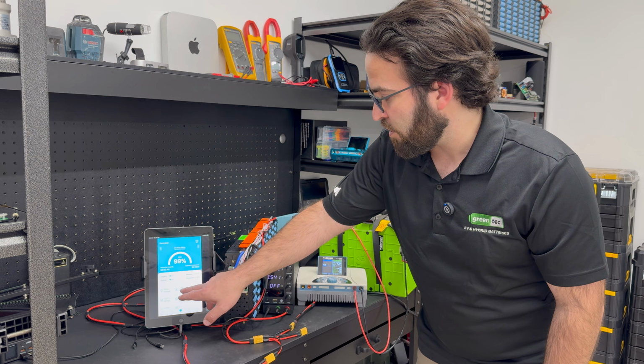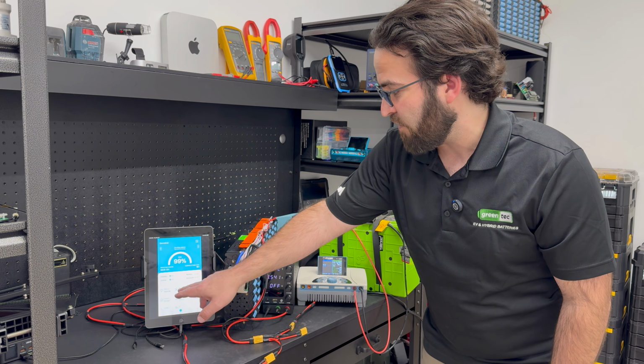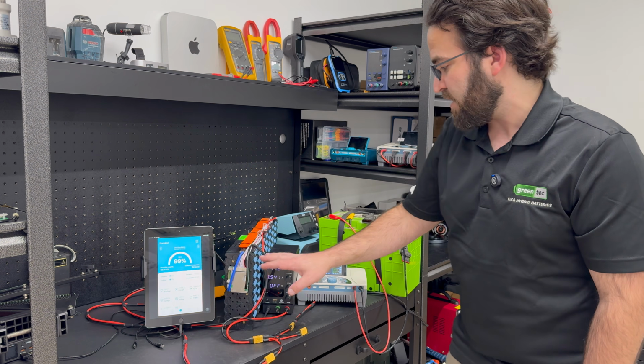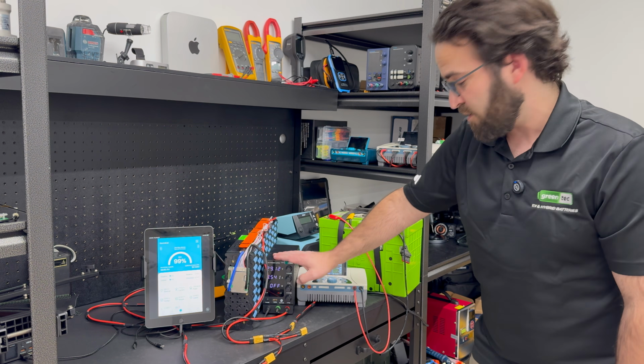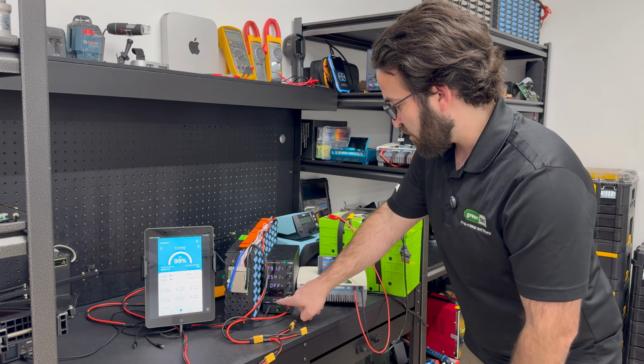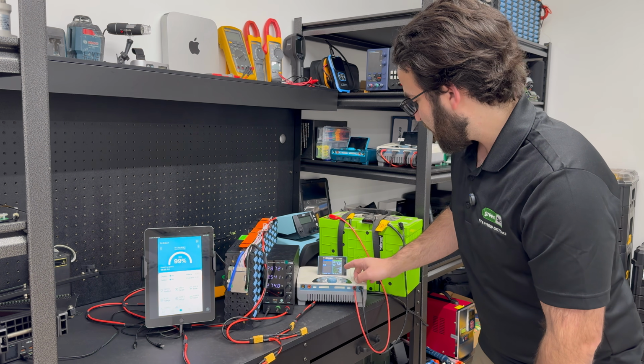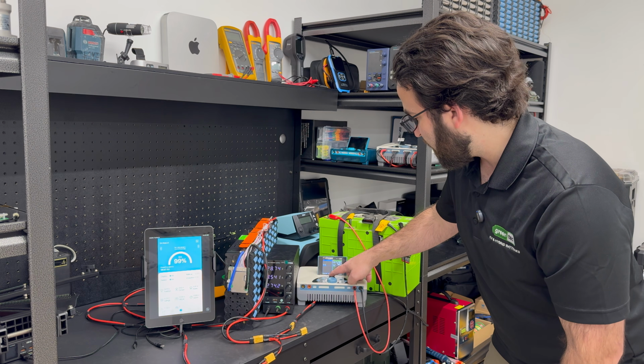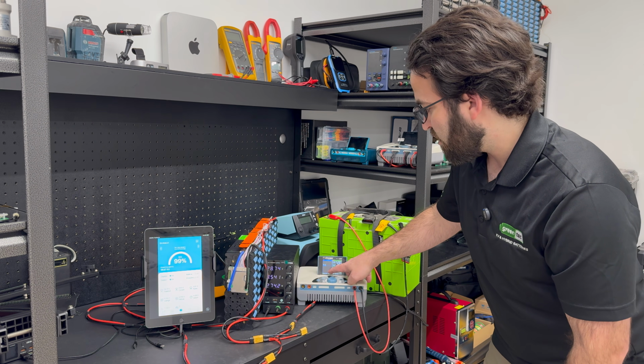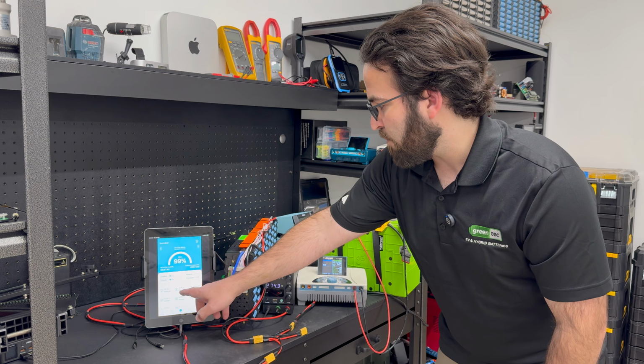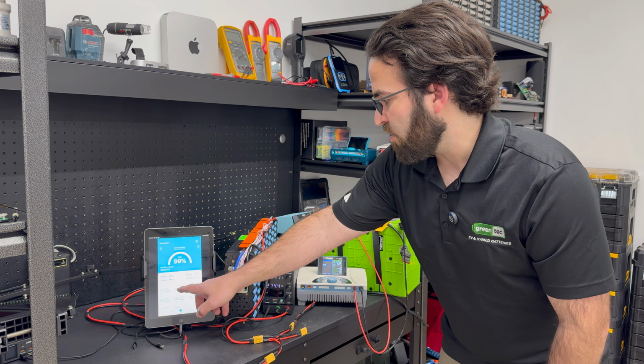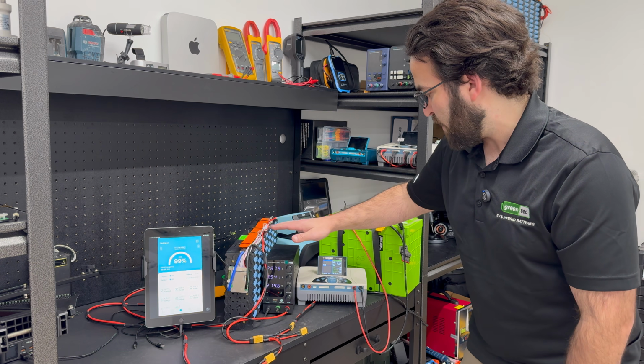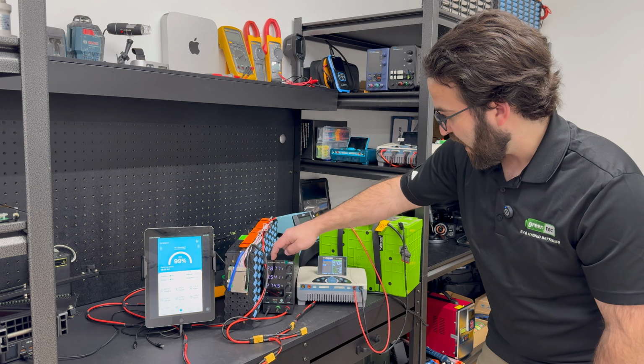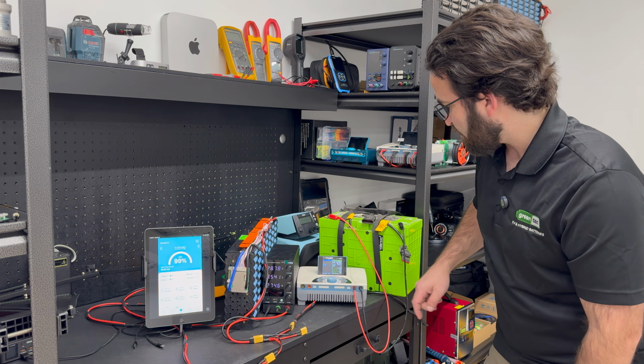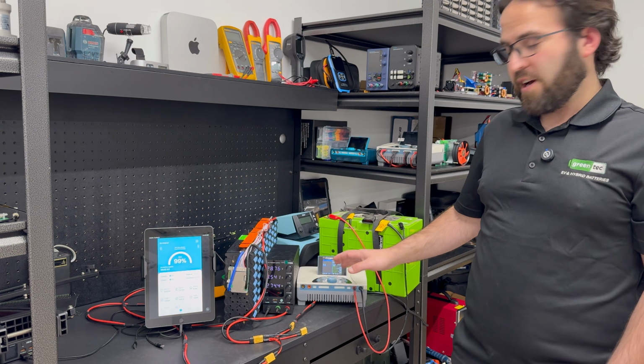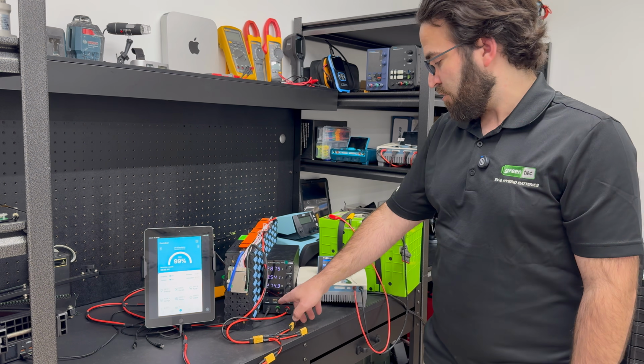All of the current, like 10 or 11 amps, is now coming directly out of the BMS itself, and nothing is coming out of the DC power supply. Now, if I turn this DC power supply back on, we still have all the amperage coming into here, but now we only have a little bit of amps coming out of the BMS, and 9.5 are coming out of here. So again, nothing got interrupted with this, whether we turn it on or off.